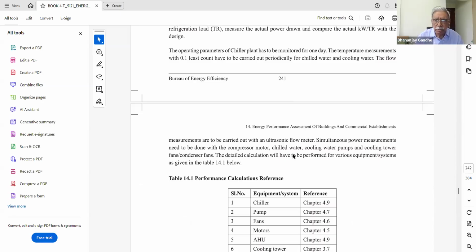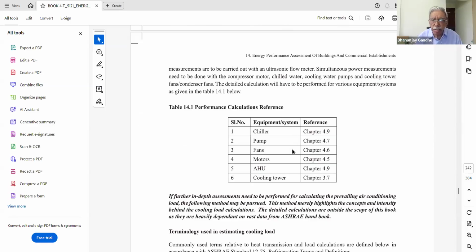and also measure the kilowatt present. We all know that an air conditioning system basically has four major components. One is, of course, the chiller or compressor, which is a major device in the air conditioning system. Then you have the chilled water system, the cooling water system, and the cooling tower. What we are talking of is not an air conditioner, but an air conditioning system. When an air conditioning system is installed for cooling a building, there will be an air conditioning plant, and we have to find out the kilowatt of the compressor, the kilowatt rating of the chilled water pump, the cooling water pump's kilowatt, and the load of the cooling tower. And we have to assess each of these components for their performance.